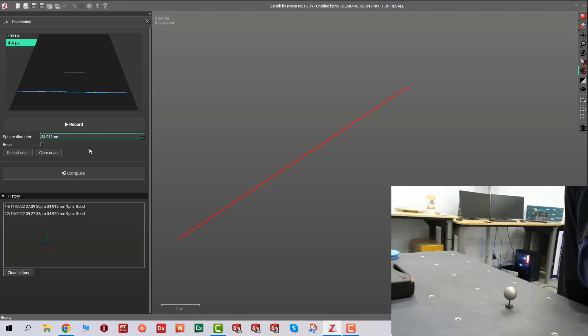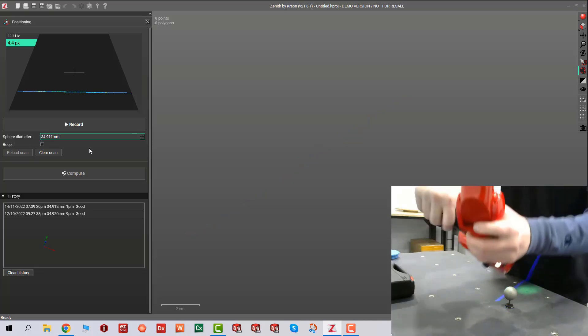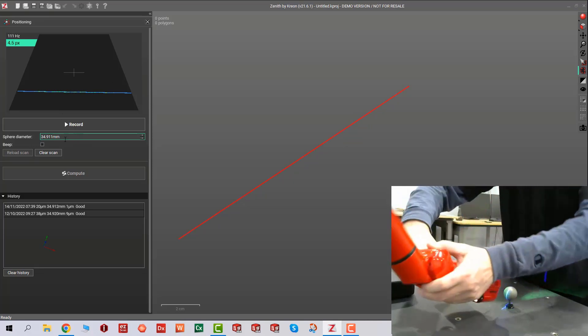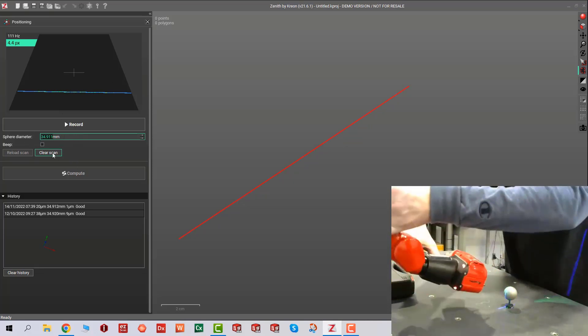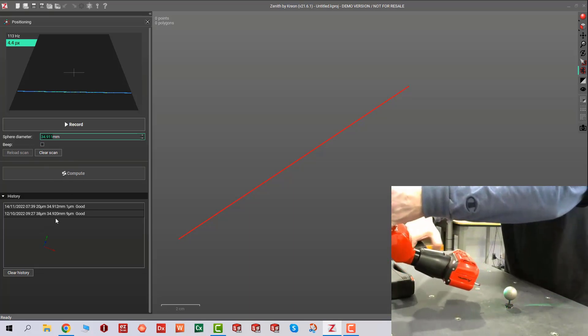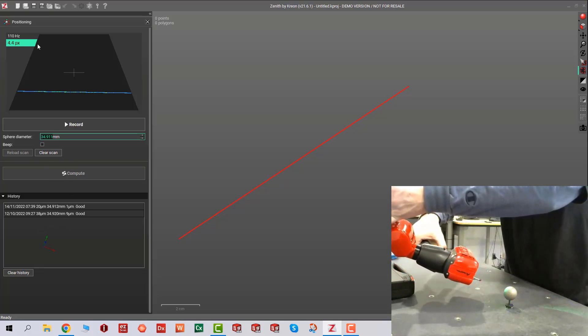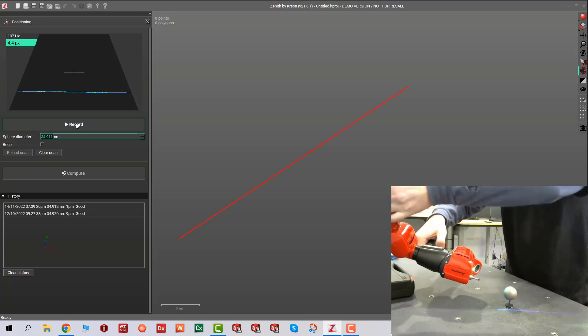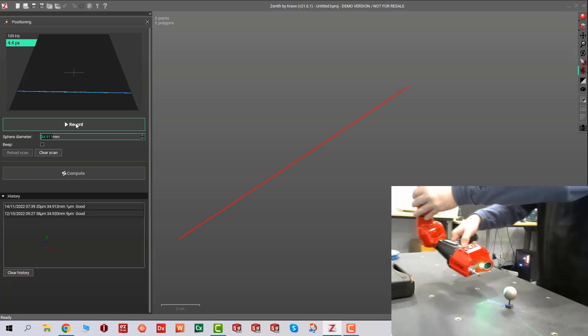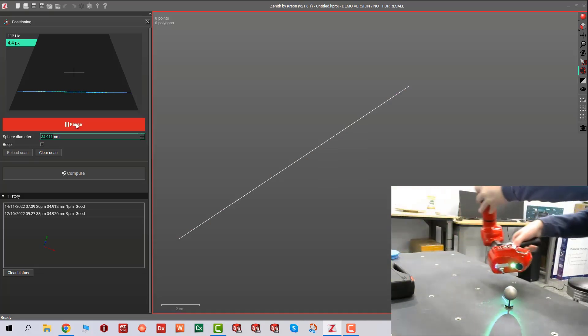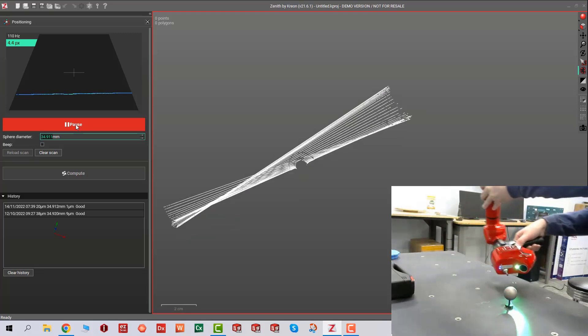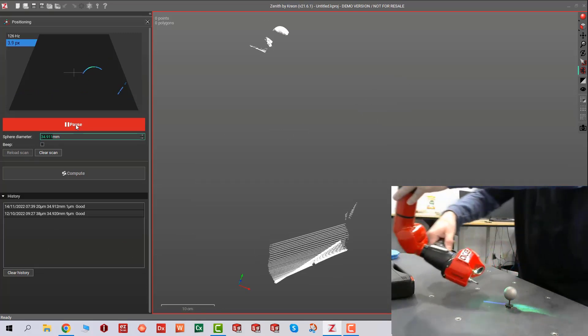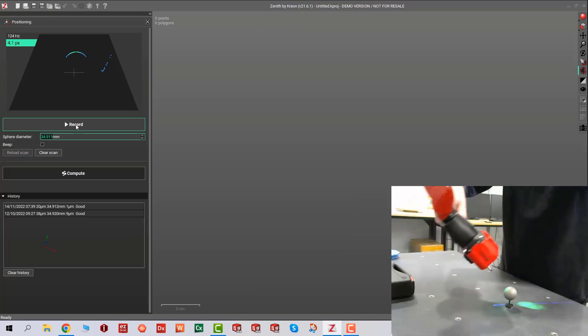We'll see that our laser is activated. Make sure you change the number if it's different, then start calibrating. I already had two calibrations done if you look at the history, but we'll do another one to show you how easily you can calibrate your probe and scanner head.